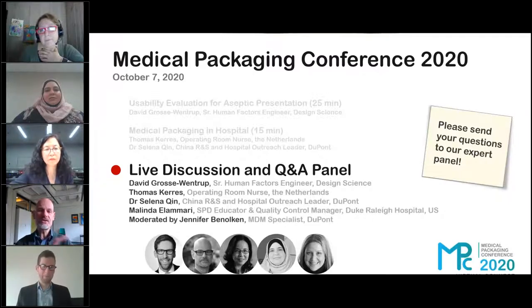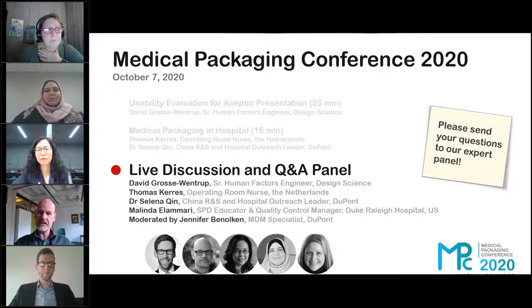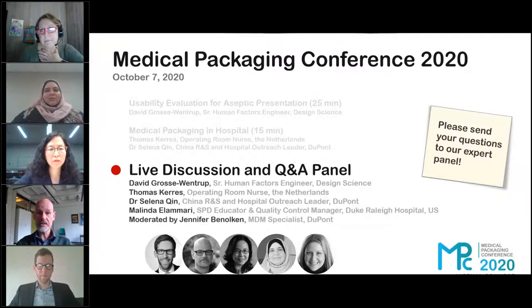The second situation was where a producer of orthopedic implants used two different sets of packages which were labeled in the same way. Due to a shortage of staff I couldn't make a clear video of that, but usually an orthopedic prosthesis is wrapped in a plastic bag, which is then put into a plastic box inside a second plastic box. Usually the inner plastic box is already sterile. This company had 50% of the products delivered in both packages sterile, while in the other 50%, we opened the first layer of packaging and the second layer was not sterile — but we still took it onto the sterile field, not knowing that it wasn't sterile. Fortunately no patient suffered any severe infection, but I can imagine you're equally shocked as we were when we heard that this package wasn't sterile.